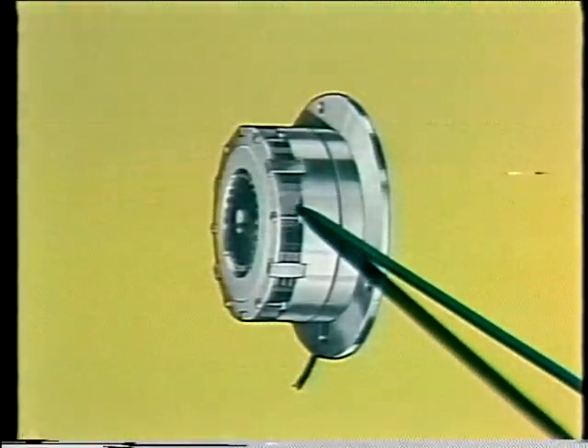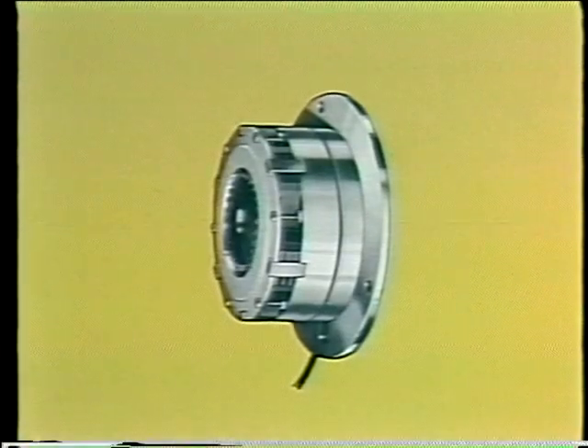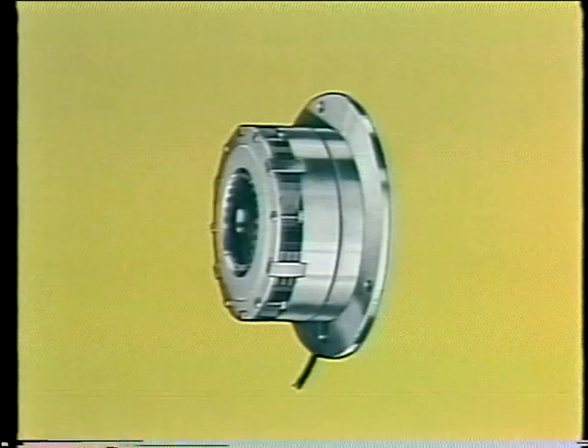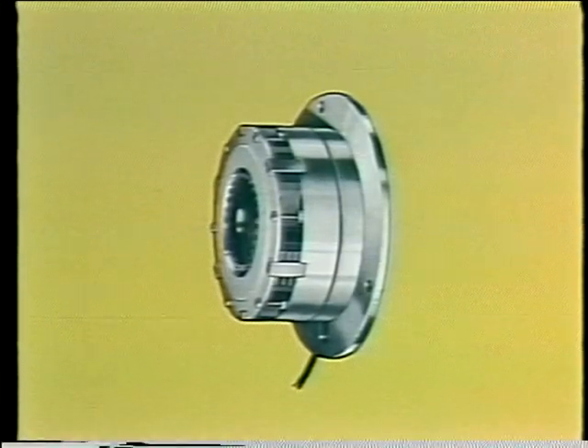If it is multiple discs, we tend to compound the problem of heat dissipation. However, we do get a very high braking capacity in a small area because we have a large friction surface. If, however, the stops are infrequent and space is at all a problem, the multiple disc unit is usually a good choice. In certain applications where there is constant slip, such as on a drag brake type, the unit may be cooled by circulating water through special cooling circuits cast right in the housing.